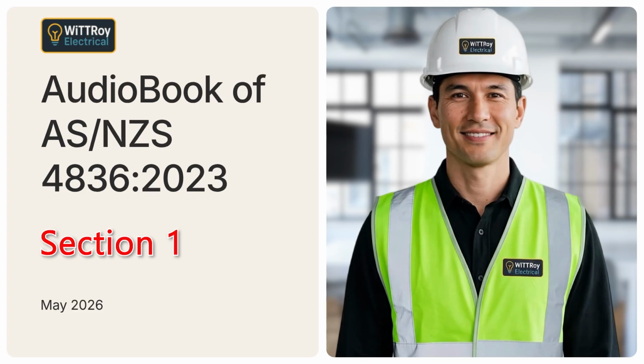Clause 1.4.41.2. Low voltage. Low voltage, or LV, means voltage higher than extra low voltage, but not more than 1000 volts AC or 1500 volts DC. This is the main voltage range covered by AS/NZS 4836. Clause 1.4.41.3. High voltage. High voltage, or HV, means voltage higher than low voltage. In simple terms, if the voltage is above the LV range, it is HV.